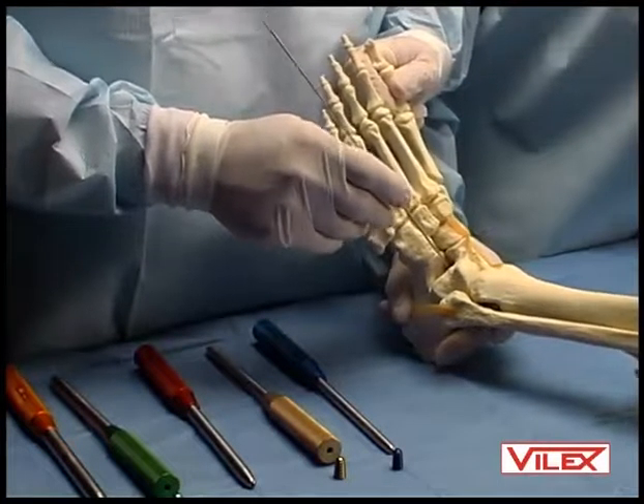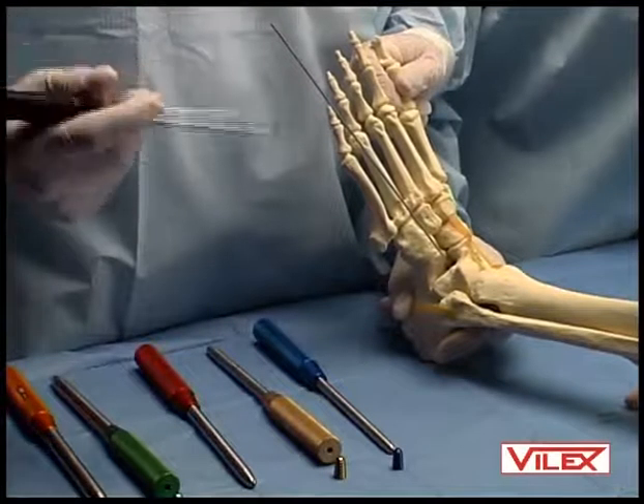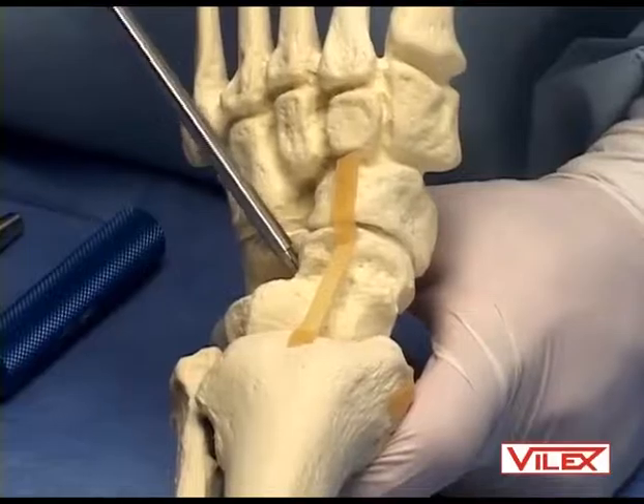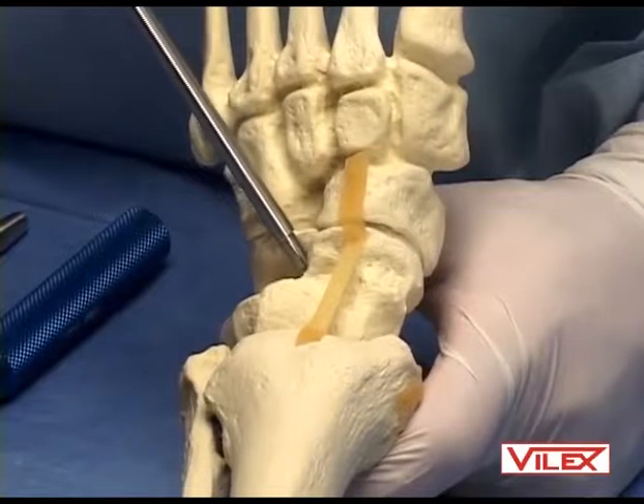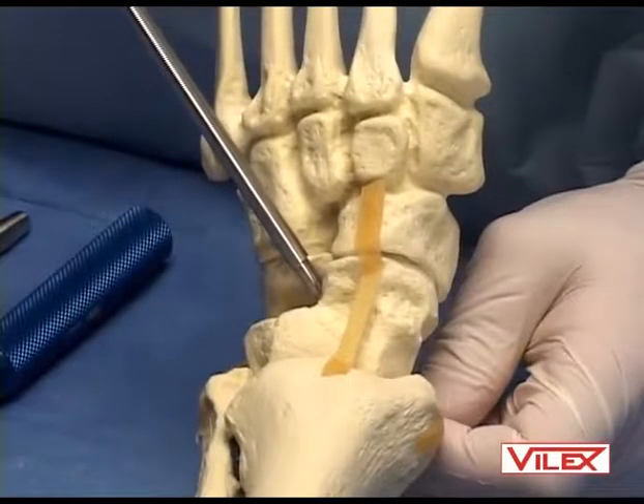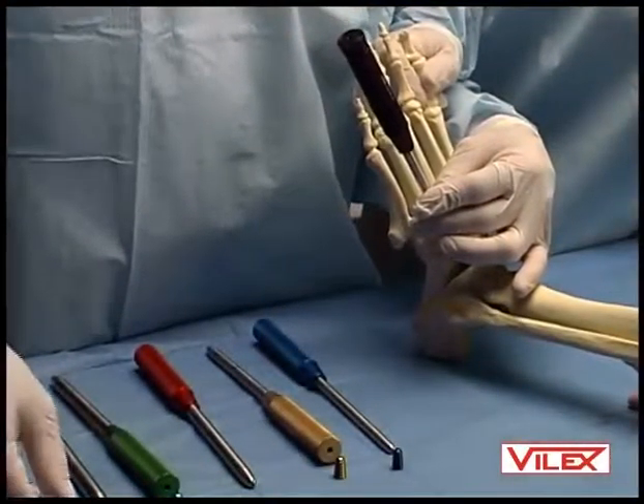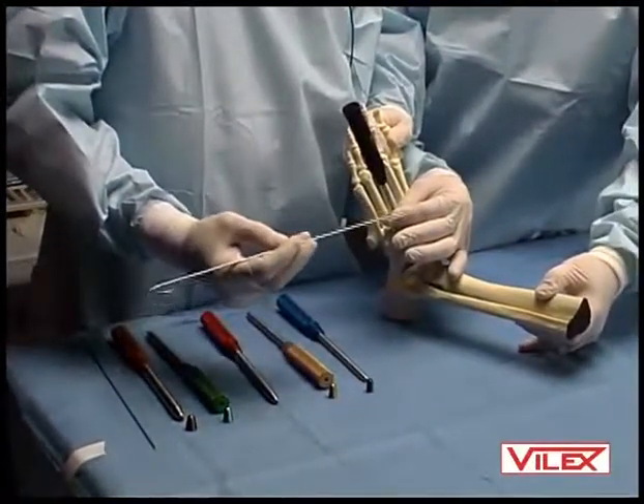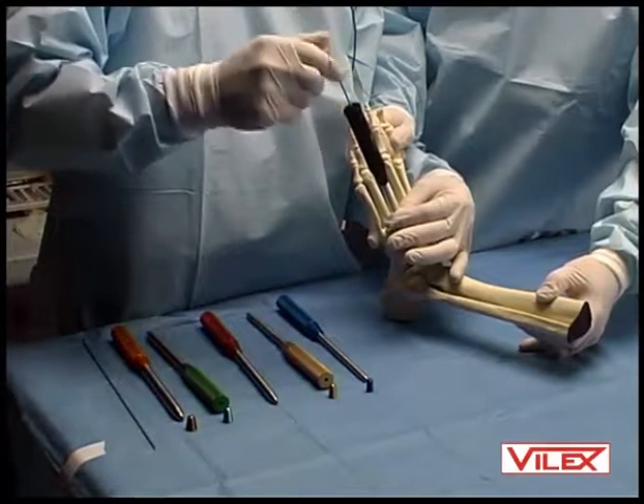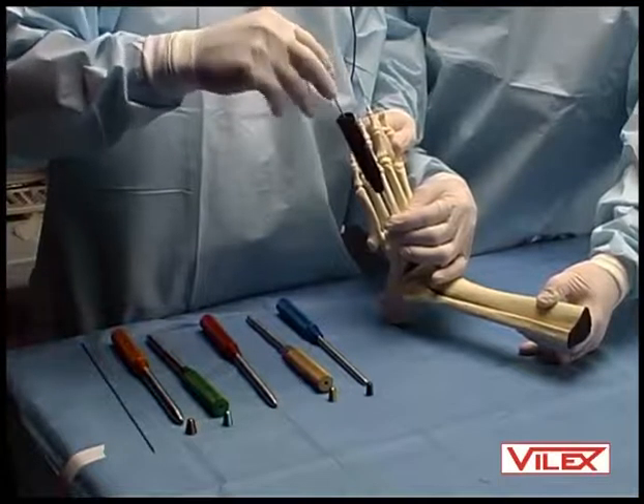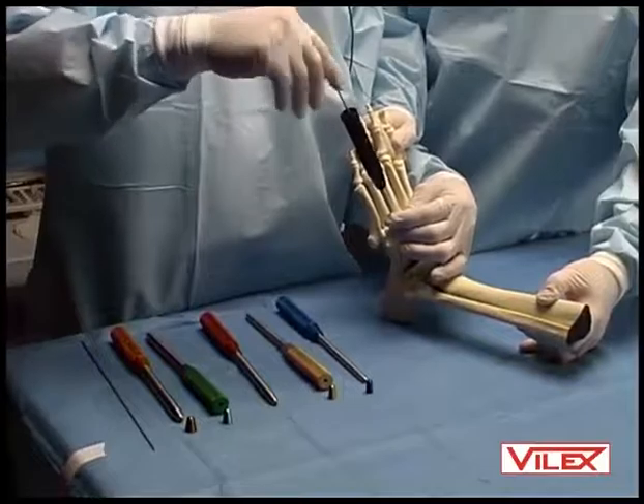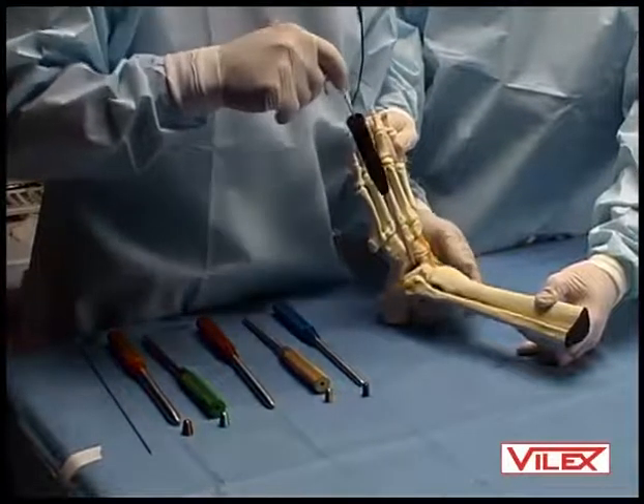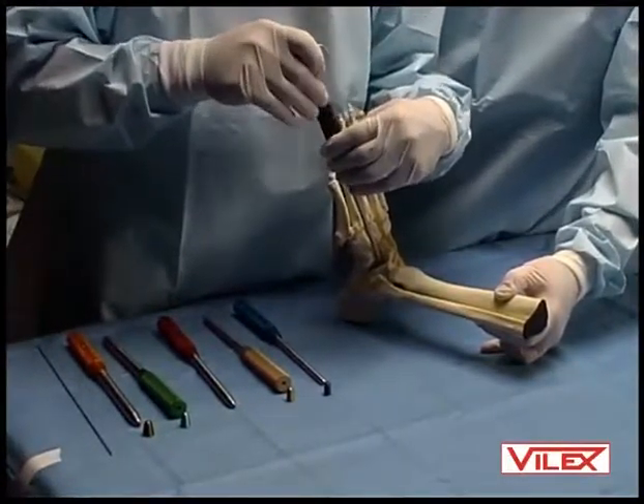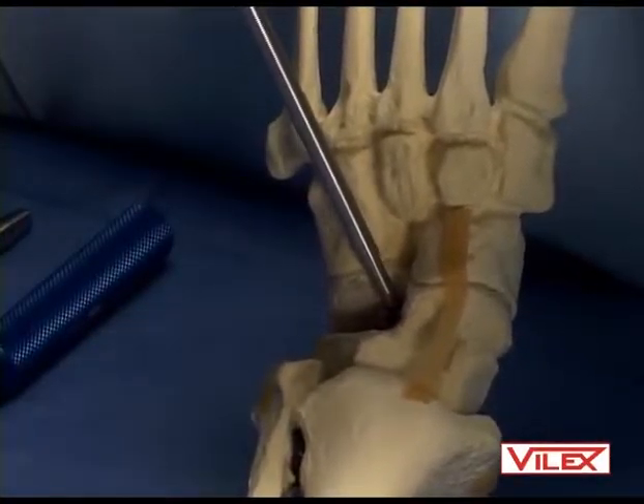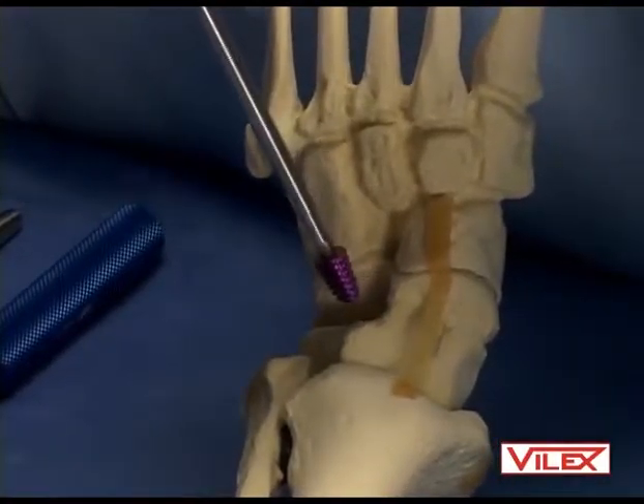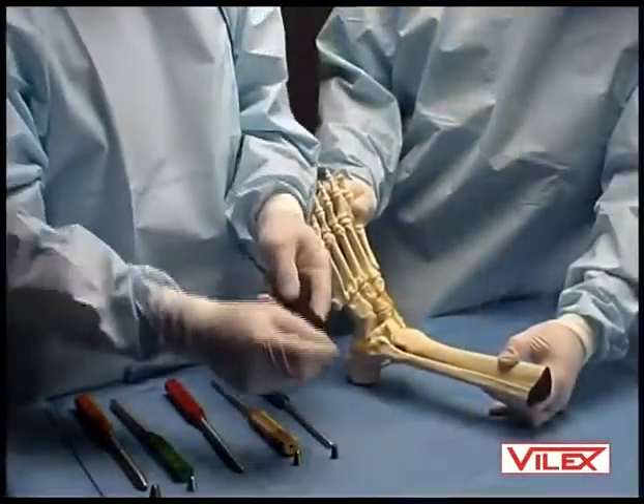We've determined that this size implant is inadequate, so now we want to remove it. As we start to remove it, it should come out. If we encounter spinning where the implant is starting to turn, but yet it's not coming out, what we can do is take the guide wire out, leaving the screwdriver in place, and pass the specialized removal tool, which has threads that will thread into the actual implant in a reverse fashion. So you're going to turn this counterclockwise so it engages into the reverse threads in the cannulation of the actual implant. Once you feel it's engaged, you can actually turn the screwdriver, and while pushing down and turning the screwdriver, it will let the implant come out in one fell swoop by pulling on the hook design of the removal tool.